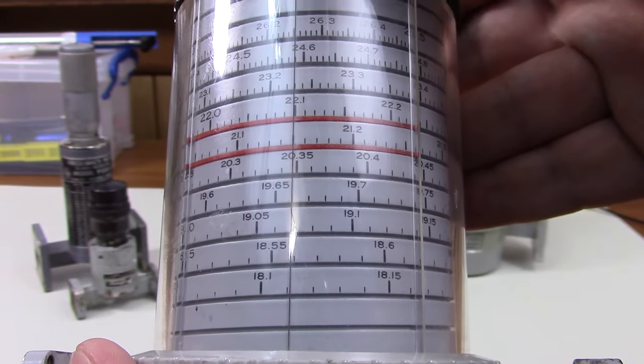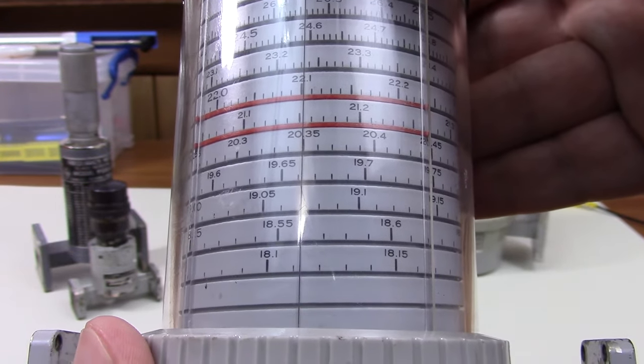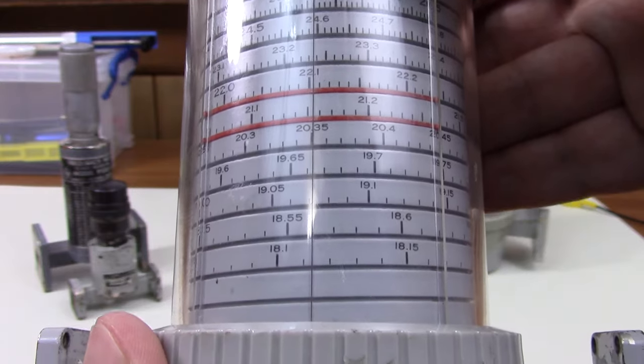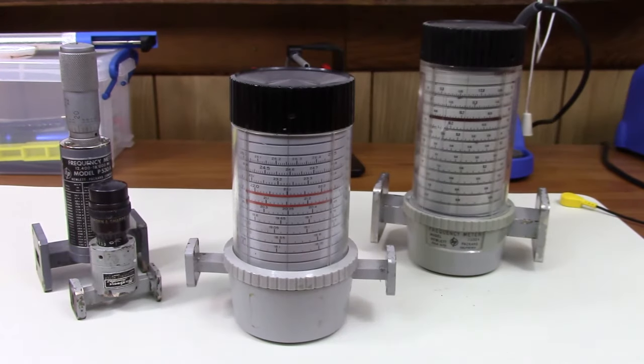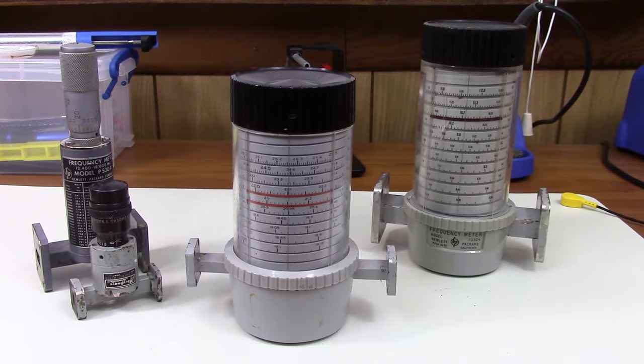If you've got a good eye you can get a little bit more accurate. However, those cavities are temperature sensitive and they age, so for really being able to read that precise you need some sort of reference.